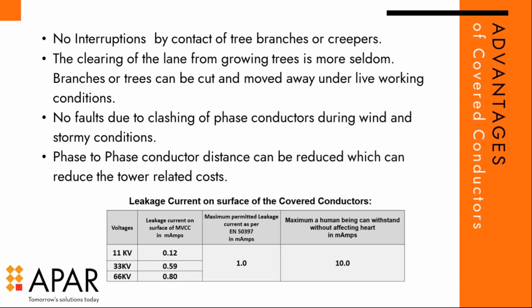The leakage current, as I told you, should be less than 1 milliamp. When we tested the technology, at 11 kV it came out to 0.12 milliamps, at 33 kV 0.59 milliamps, and at 66 kV 0.80 milliamps. This is well within the limits, and the human heart can sustain up to 10 milliamps.